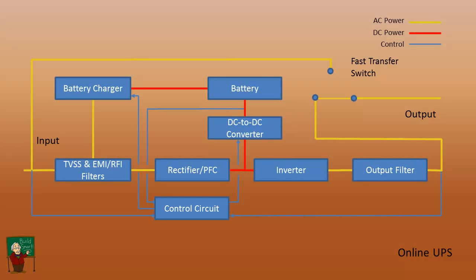Then it'll look at the output voltage and have the ability to operate the transfer switch. And finally, there'll be some alarms, and the control circuit will be able to turn on those alarms. So when we power this unit up, we see that it provides power to the battery charger, which is not on. It goes through all the stages and provides voltage output.